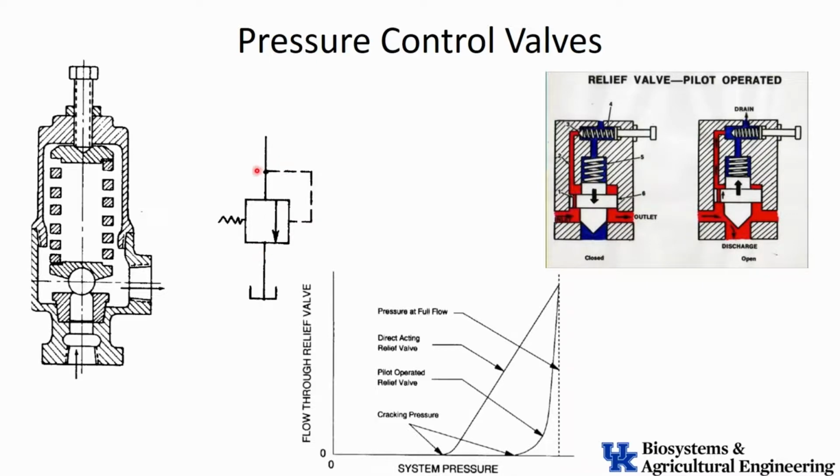Okay? And so what forces that block over is this pressure sensing line up here. And we talked about these with the pump. So this is just a line that senses pressure. It's a very small port, usually within a valve. And it could even be more simple than that. When we look at the valve over here, we'll see it's just really, really basic. But in function, it says, okay, we're going to sense the pressure upstream. When that pressure gets high enough, we're going to allow this block to work against the spring over here, push that block over and allow flow to go through. So when the pressure gets high, we open up and allow flow to go through. So it's like a relief valve or a safety. So, we put this after a pump typically to protect the pump.